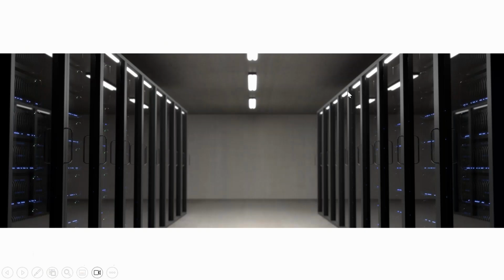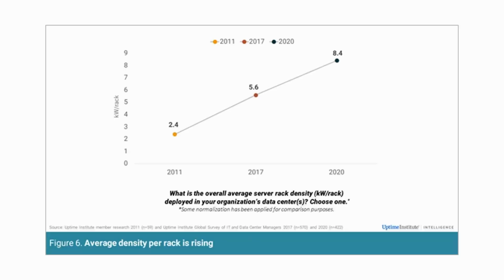So if you joined us along the way on our presentations, you know we're always talking about heat density. How are the heat densities changing? What all these crazy chip manufacturers are doing to the rest of us that we have to respond to? So a few years ago, chip densities weren't all that hot. We could cool everything just fine by traditional air-cooled methods, but obviously some things have changed. I like to always harken back to the Uptime Institute's data where they showed us what happened during the 2010s. So here is an average heat density per rack measured in kilowatts. So in 2011, they were reporting, and this is survey data, so it's not totally holistic, but their survey respondents told them, somewhere in 2.5 kW per rack. And then by the end of the 2010s, we were at 8.4 kW per rack, which seems like tremendous growth. That's 3.5 times as much heat density over a 10-year period. That's quite a big growth.